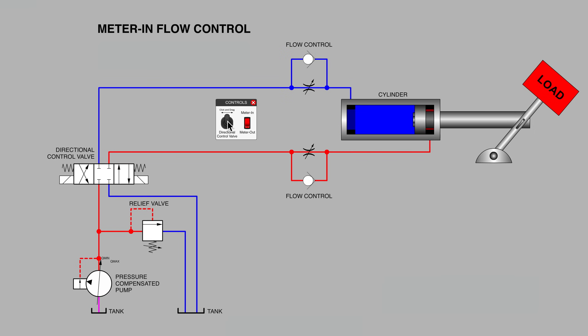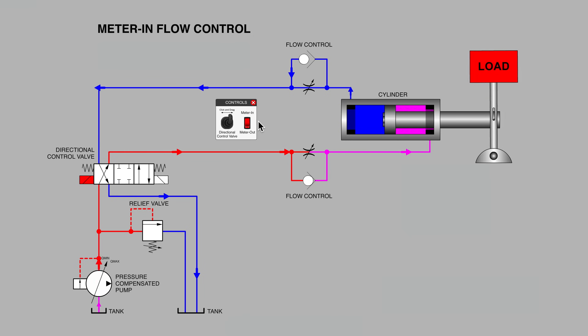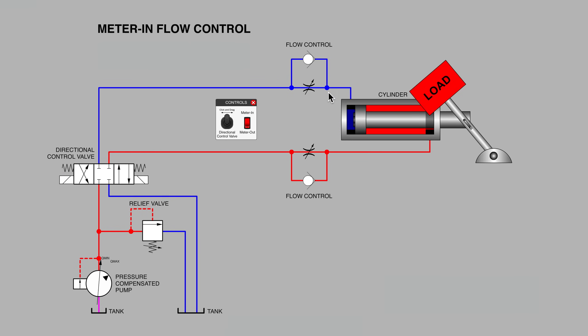Now let's watch meter in flow controlling taking place on the line that feeds the rod end port. This will be meter in for the retracting of the cylinder. You could see that fluid is being metered on the bottom line and oil leaving the blind end port can do so freely through the return flow check valve mounted in parallel to the needle valve. Let's work forward and back again.